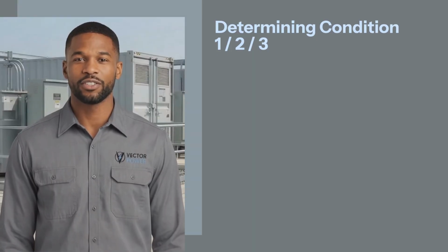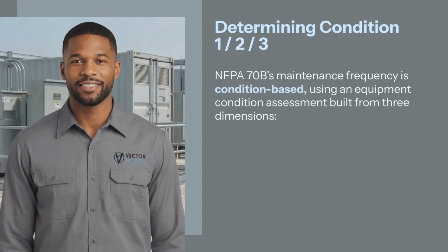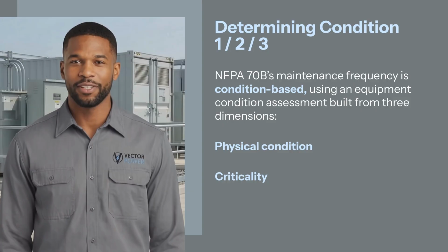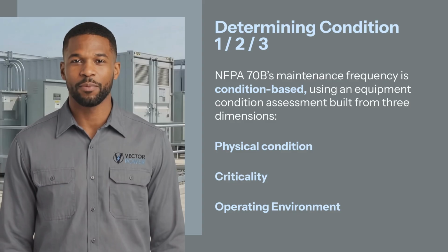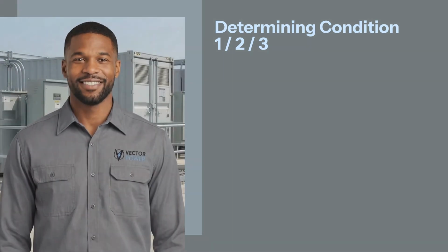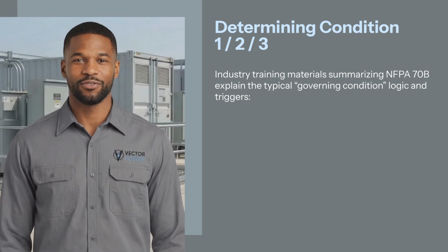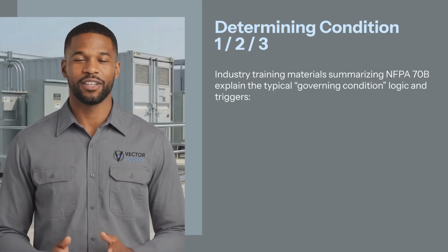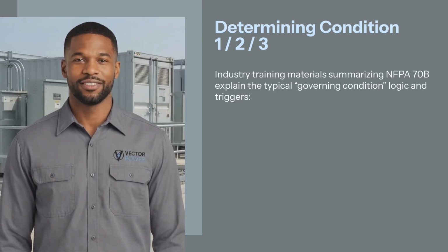Determining condition 1, 2, or 3. NFPA 70B's maintenance frequency is condition-based, using an equipment condition assessment built from 3 dimensions: the physical condition of the equipment, the criticality of the equipment, and the operating environment in which the equipment is being used. Industry training materials summarizing NFPA 70B explain the typical governing condition logic and triggers.